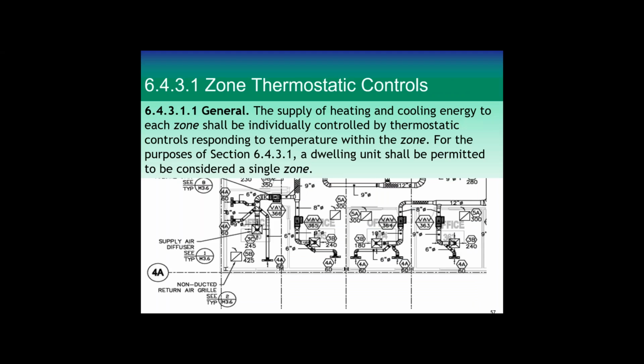Now, the thermostat controls I always like to mention, because does it make sense that we're making a deal out of it? Well, the supply of heating and cooling energy to each zone shall be individually controlled by thermostatic controls responding to the temperature within that zone. For the purpose of this section, a dwelling unit shall be permitted to be one single zone. So if you've got a little apartment with a bedroom, a front dining room, and a hall, that can be considered one zone, not the dining room separate from the den. Anyway, you can see that it's one thermostat per apartment.